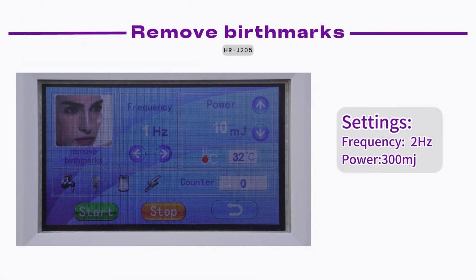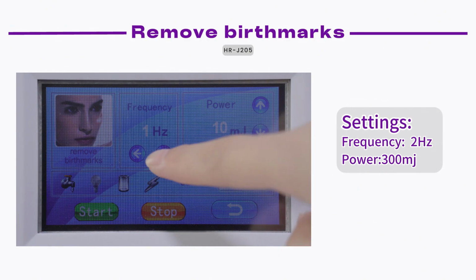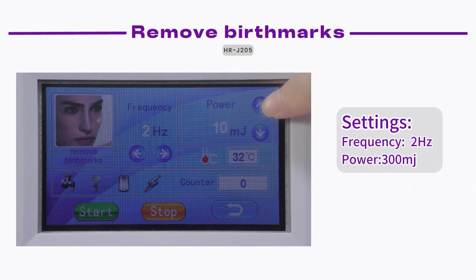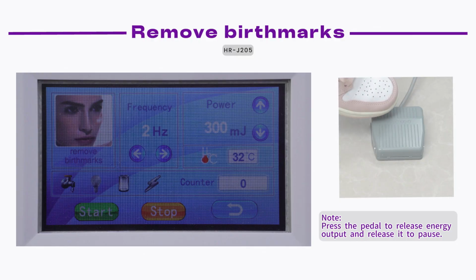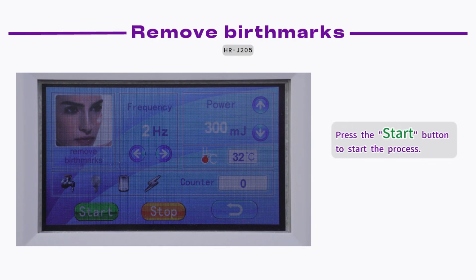Choose Remove Birthmarks. Settings. Frequency, 2 Hz. Power, 300 mJ. Note, press the pedal to release energy output and release it to pause. Press the start button to start the process. Press the stop button to halt the operation.